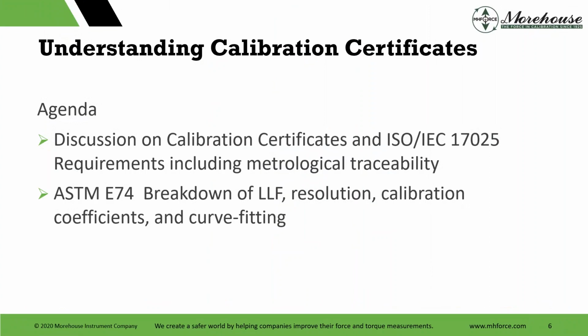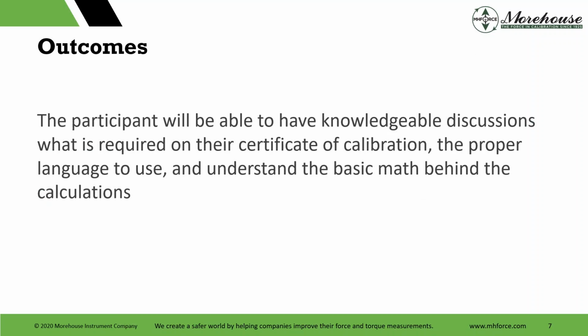Today, as I said, we're going to discuss calibration certificates and ISO IEC 17025 requirements, including metrological traceability, very important there, and ASTM E74. We're going to break down the LLF, which is the lower limit factor, resolution, how to calculate resolution, calibration coefficients, and curve fittings. The desired outcome is that you as a participant will be able to have knowledgeable discussions about what is required on your current certificates of calibration, the proper language to use, and understand the basic math behind the calculations.